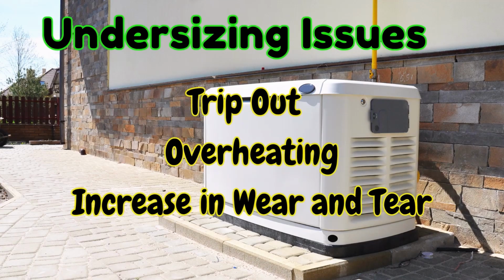So what are the consequences of incorrect sizing? Undersizing or oversizing a generator can lead to various issues. If your generator is undersized, it can firstly trip out. The generator may trip out when the demand is higher than it can produce, leaving your facility without power during an outage. It can also overheat.